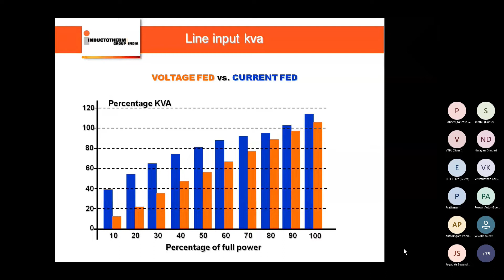So line input kVA exactly implies the same thing: when the power factor is constant, the kVA is exactly proportional to the kilowatt. So the kVA will never be demanded due to the power factor when you are operating at lower kilowatts on the induction furnace. The orange shows Inductotherm's kVA requirement for a given kilowatt. The blue shows the kVA requirement for other design manufacturers.